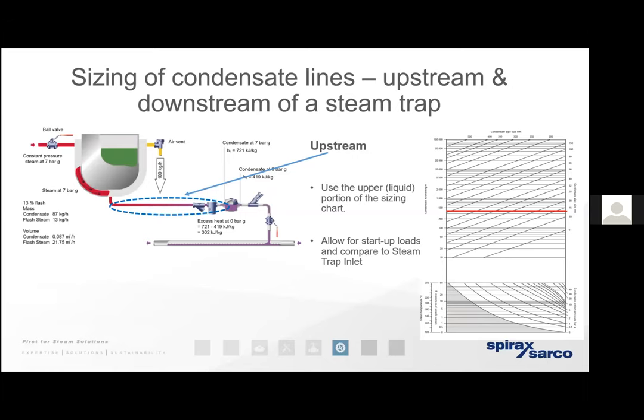Just as steam condenses far more readily in cold distribution pipework, the same is true at the process, so we want a safety factor of ideally times three. If we sized the pipework to accommodate only 100 kilograms per hour and the system was starting up from cold, the increased condensate load could back up ahead of the trap and slowly start to flood the process. The chart on the right-hand side of the screen enables us to correctly size condensate pipework under pressure, and you can refer to that useful app for assistance on correct condensate pipe sizing.